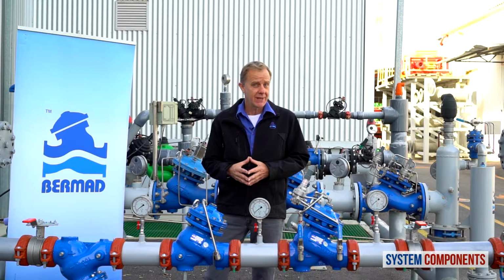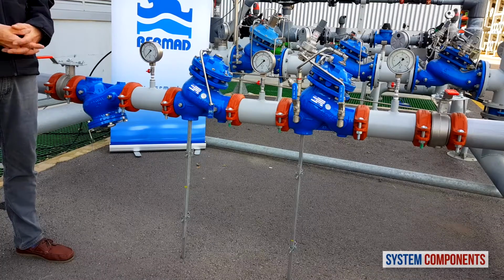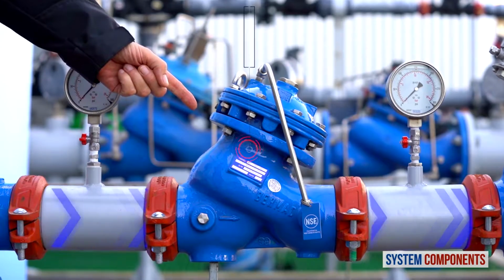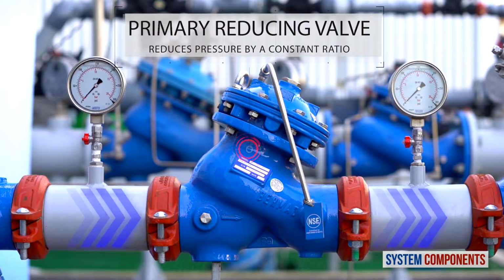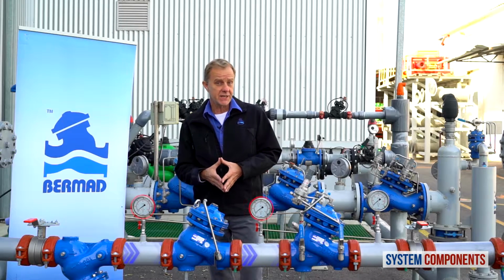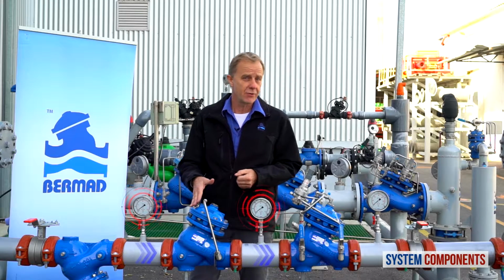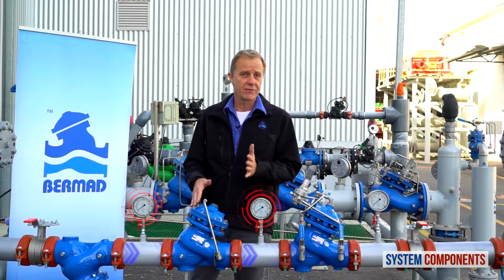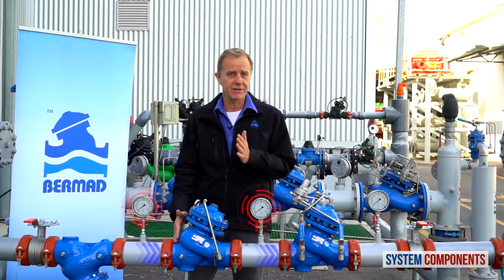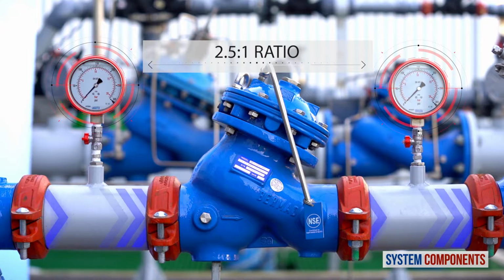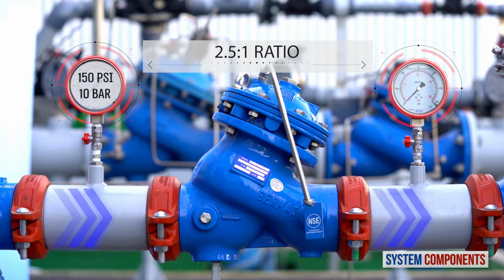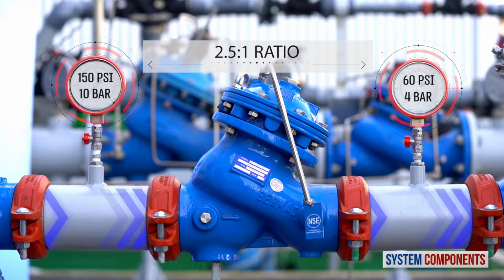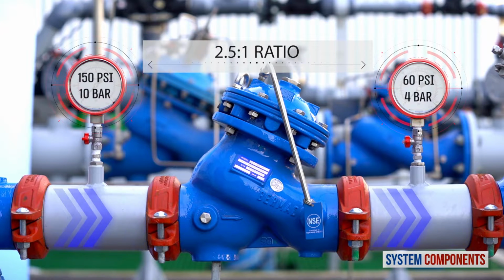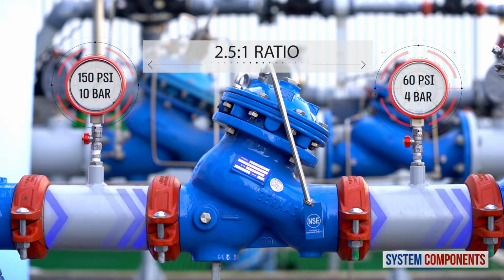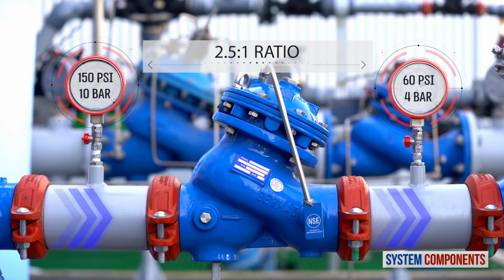Now let me briefly explain how this station works. The primary pressure reducing valve is proportional, and as mentioned before, it reduces the pressure by a given ratio. In this case, we are using a 4-inch valve, so the ratio is 2.5 to 1. So divide the valve inlet pressure by 2.5 to get the valve outlet pressure. For example, if the pressure at the valve inlet is 150 psi or 10 bars, the pressure at the outlet will be approximately 60 psi or 4 bars, depending on the valve size and port trim. Note that this proportional valve cannot be calibrated or adjusted.